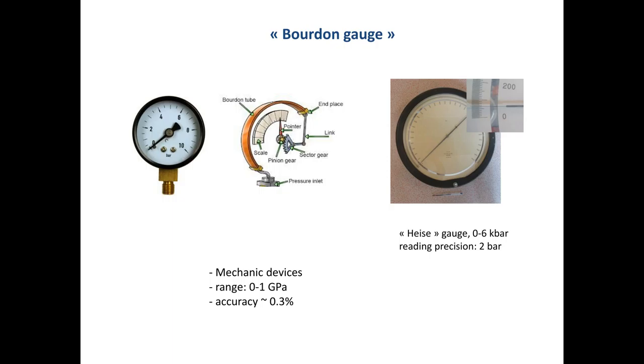There are also big devices of this type — for example the famous Heise gauges, which go to 6 kilobars; some go up to 10 kilobars. They are large — you see here, this is a pen for scale. They are surprisingly accurate because you have a reading precision of two bars, achieved by having a mirror behind the pointer to avoid parallax errors.